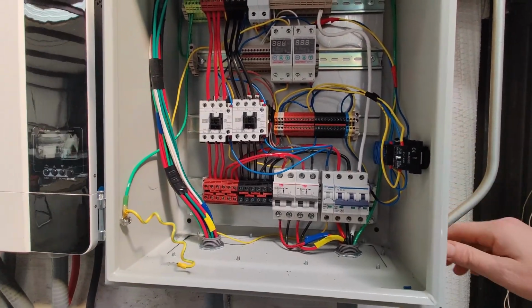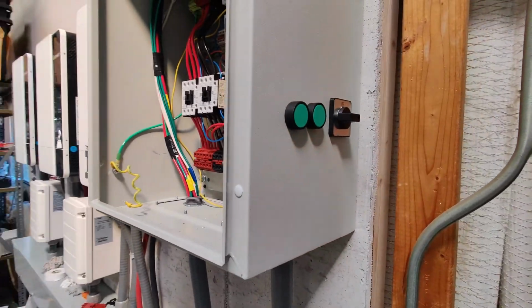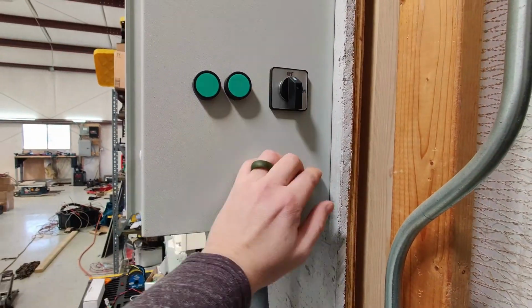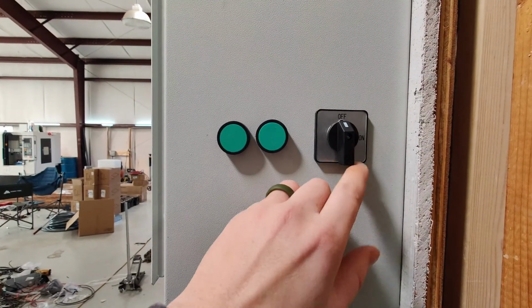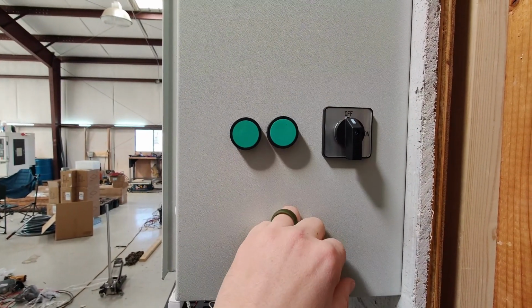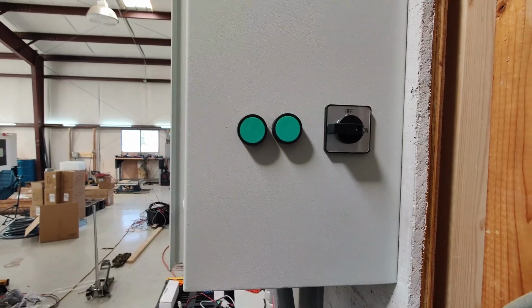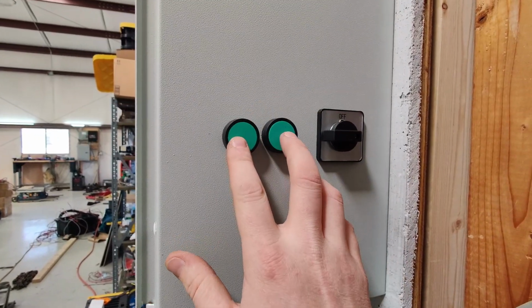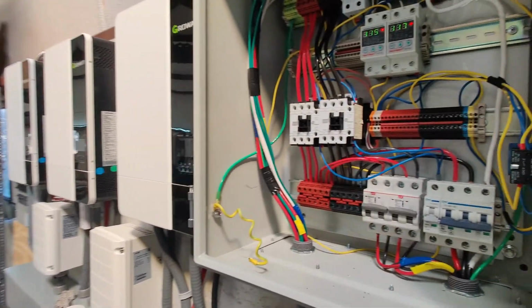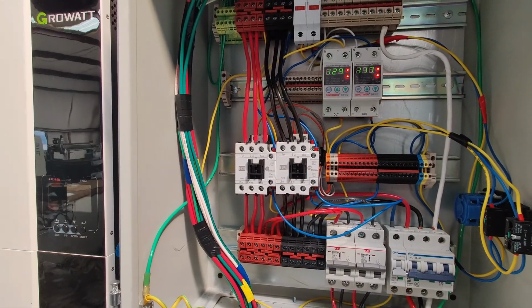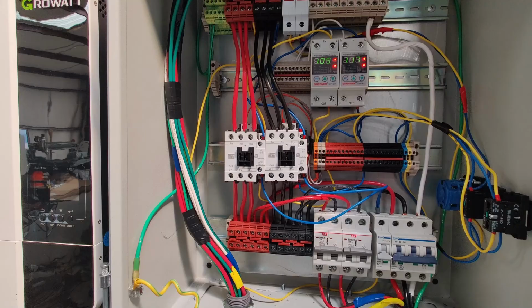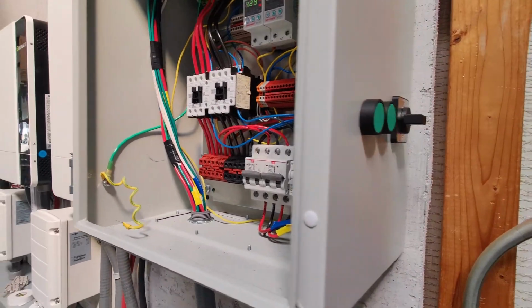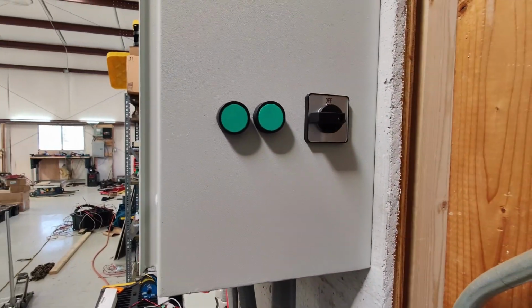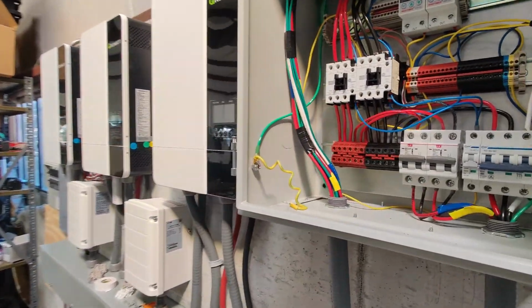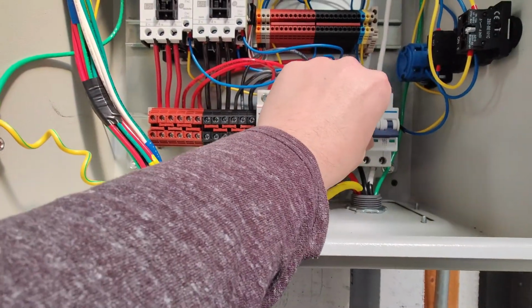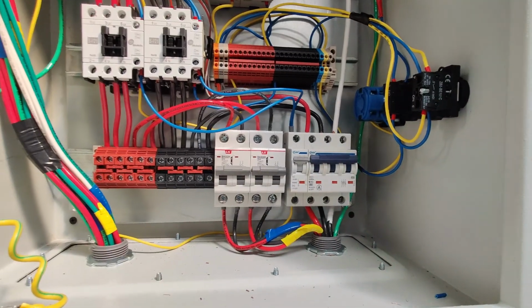So let's go ahead and walk through the steps to activate the system. So we've got our on-off switch, which I like to have so I can turn it off if I want to do maintenance or something. So we'll go ahead and turn it on. We'll push and hold these two buttons, which activates our contactor. You see the lights turned on our voltage protection relays. I'll let the buttons go, and then the system runs itself. And that's pretty cool.